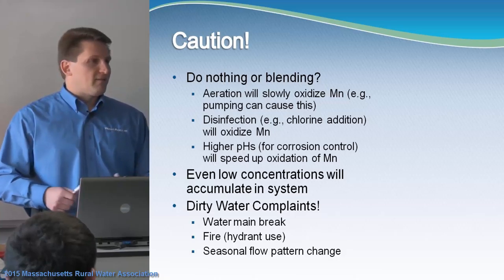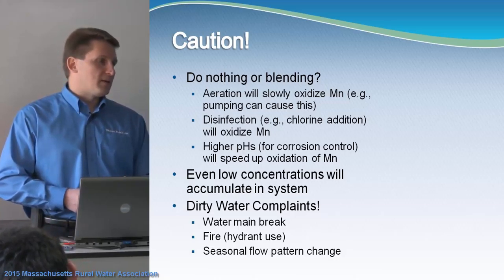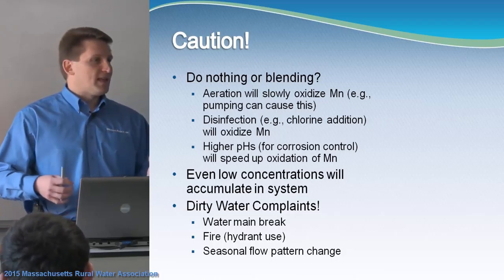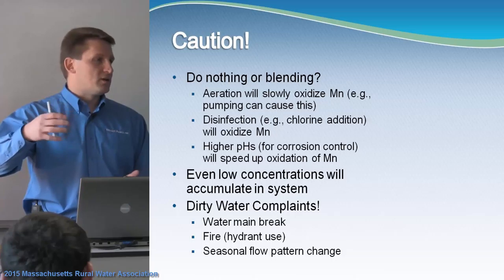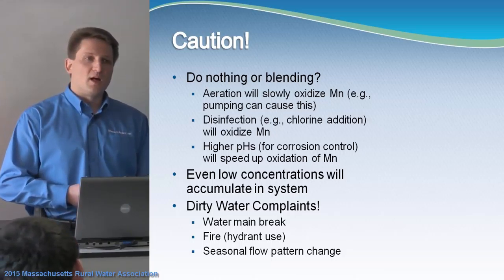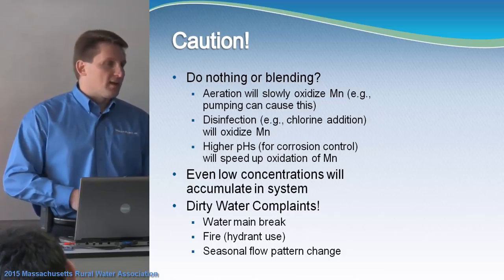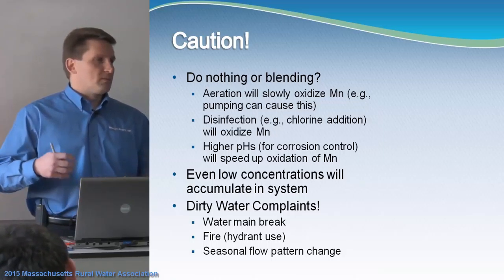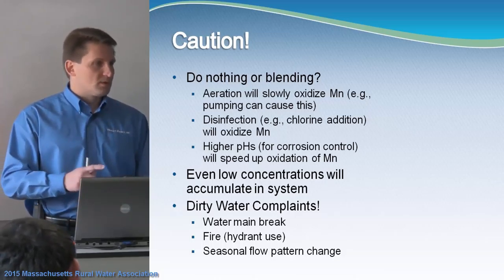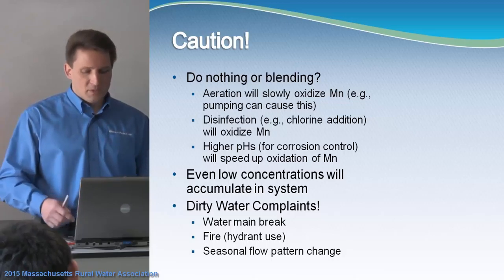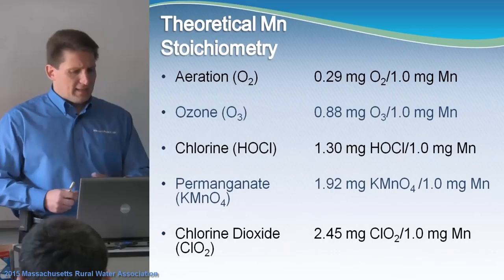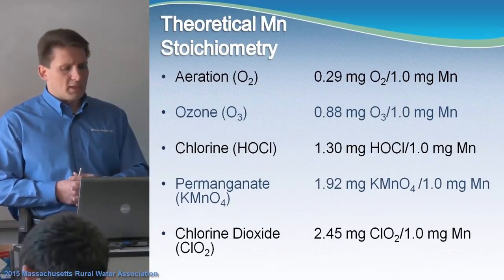It's worth noting that even if you're under the secondary MCL or the ORSGL of 0.05 mg/L, even at that low level, if you pump water into your distribution system, over time that manganese will collect, settle out, and oxidize. During a water main break, a fire, or some seasonal flow change — like when people start filling pools and watering lawns — you're going to stir that up and get a lot of phone calls.